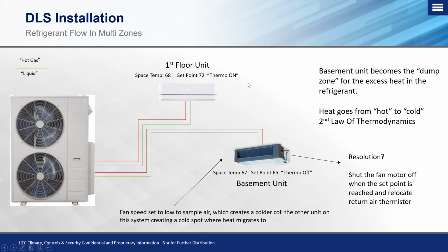Now, if we look at this from a scientific point of view, we know that the second law of thermodynamics states that heat goes from a hot to a cold surface. So in this case, this coil is going to be hotter, this coil is going to be colder. So that heat, excess heat from the system, is now going to migrate to the basement unit with this fan running. So this becomes our dump zone while we've addressed this unit to make sure that it does not overheat. Okay, so this is how we configure a two-headed system to use the basement unit, or the area that we're not concerned with space temperature, to be a dump zone.